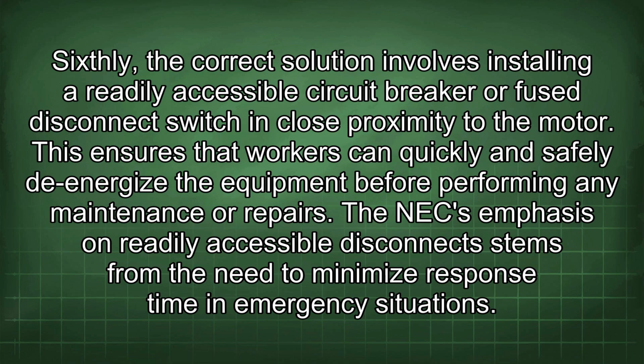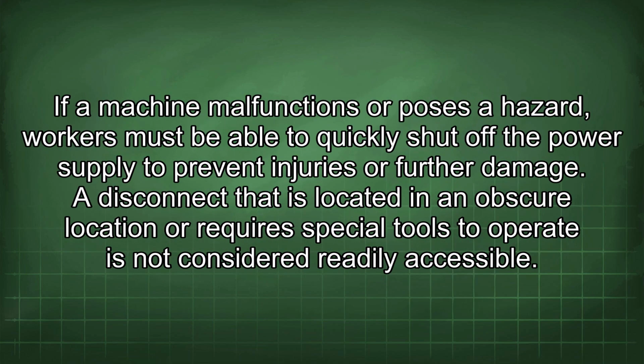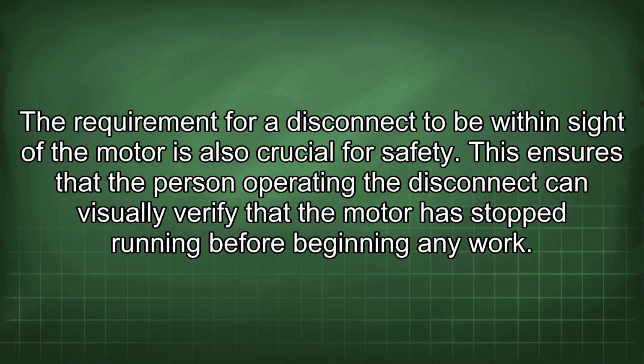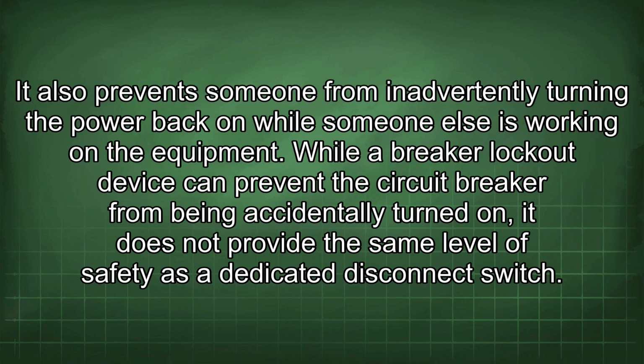The NEC emphasis on readily accessible disconnects stems from the need to minimize response time in emergency situations. If a machine malfunctions or poses a hazard, workers must be able to quickly shut off the power supply to prevent injuries or further damage. A disconnect that is located in an obscure location or requires special tools to operate is not considered readily accessible. The requirement for a disconnect to be within sight of the motor is also crucial for safety. This ensures that the person operating the disconnect can visually verify that the motor has stopped running before beginning any work. It also prevents someone from inadvertently turning the power back on while someone else is working on the equipment.